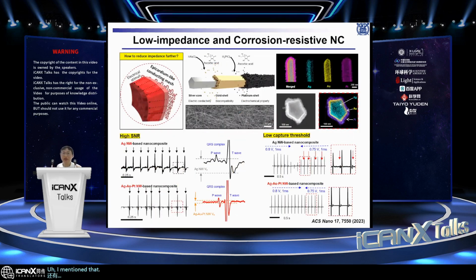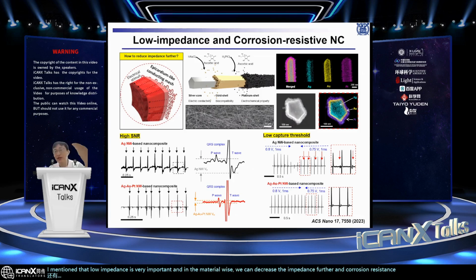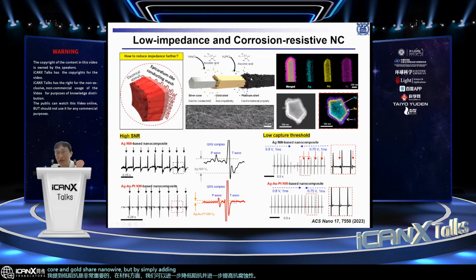I mentioned that low impedance is very important, and materials-wise, we can decrease the impedance further and increase the corrosion resistivity further. Previously, we used the silver core and gold shell nanowire, but by simply adding a platinum shell, the impedance can be even lower, and platinum has very high corrosion resistance in comparison to silver and gold. So over long-term implantation, platinum maintains its original low impedance and original electrical properties.